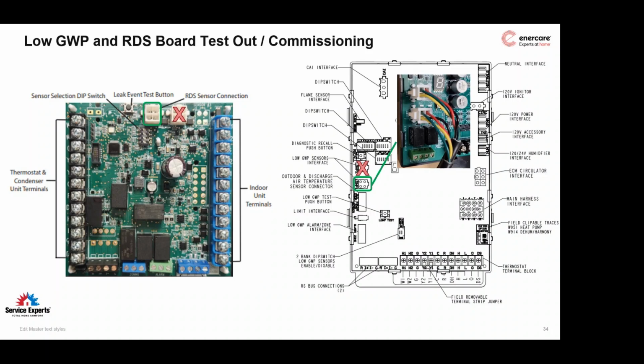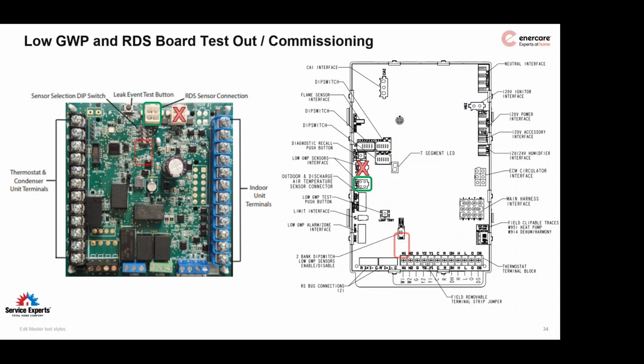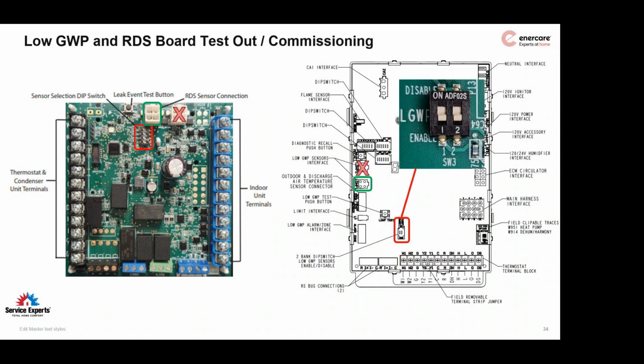Your first step before testing is to go to the dip switch settings, number 2, and move it to the on position. So again, on the left-hand side where the external RDS board is, you're going to push that to the right. And on the board in front of you, you can see on the SLP board, there's 2 dip switches. Number 2 would go up. So now the control board is really only looking for 1 leak sensor instead of 2. Now, on to testing.